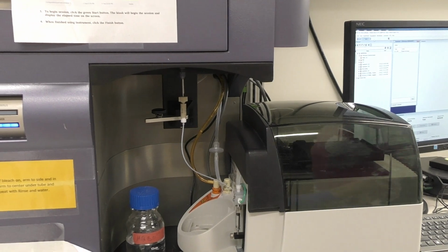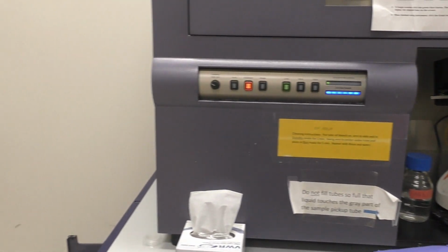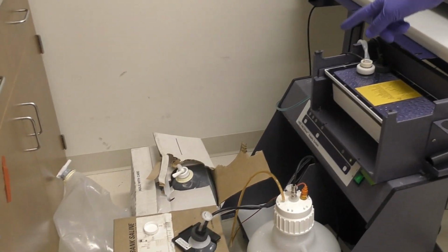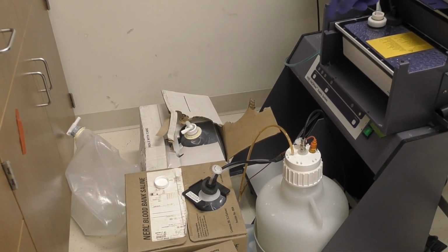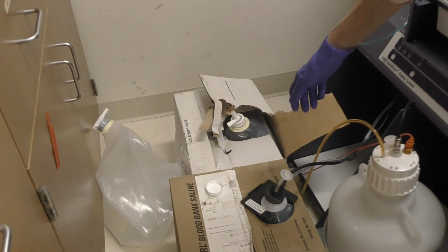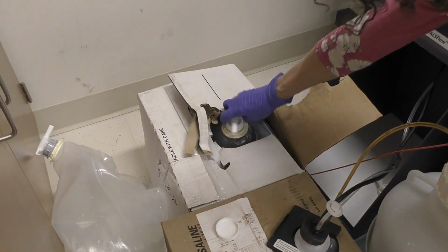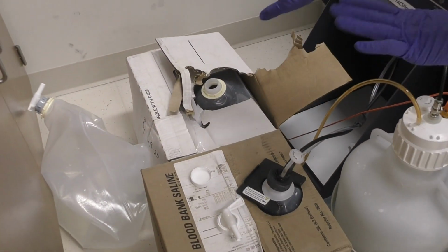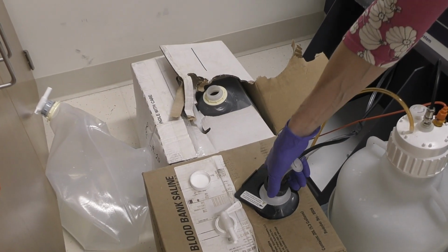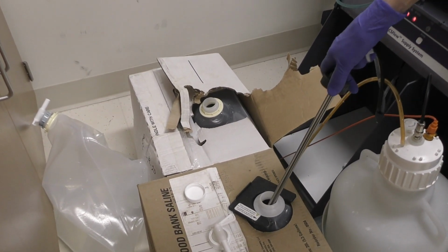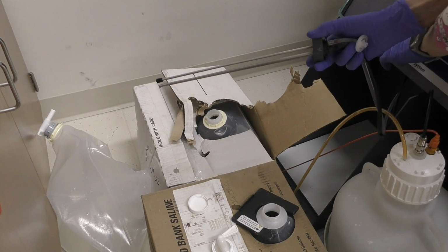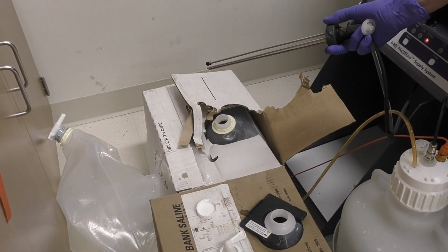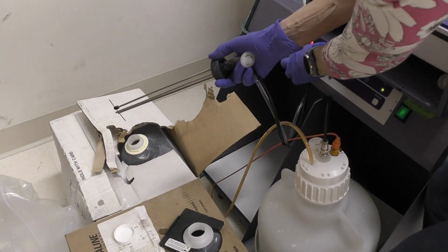Next, we're going to switch the sheath probe from regular sheath fluid over to sheath fluid with surfactant, which is recommended when you're running the HTS. We're going to take the cap off of this one. It's the white box. Remove the probe, the alarm will go off.